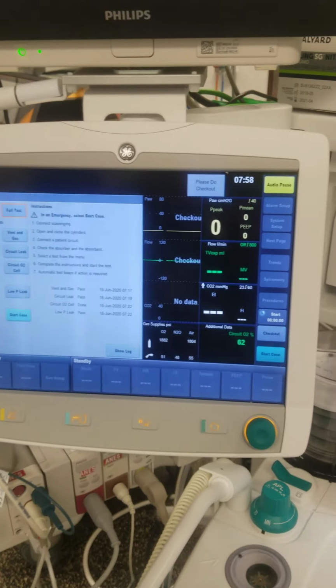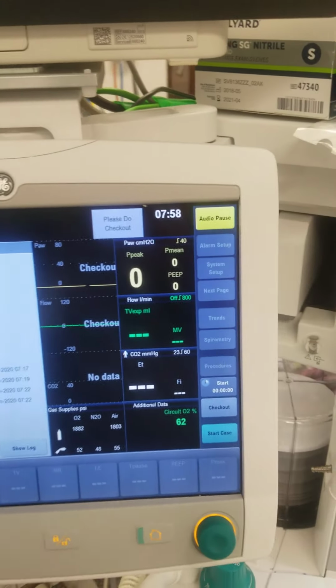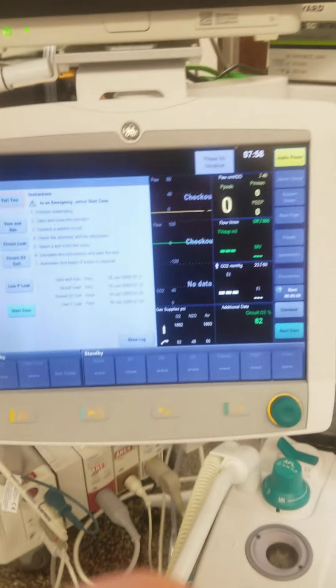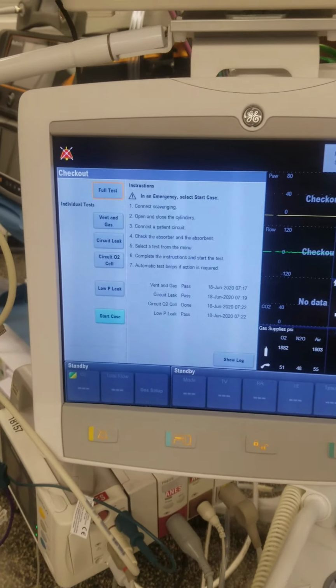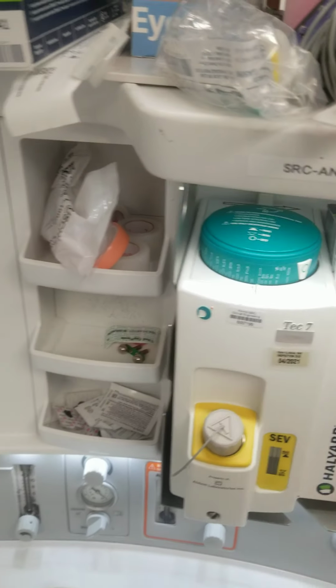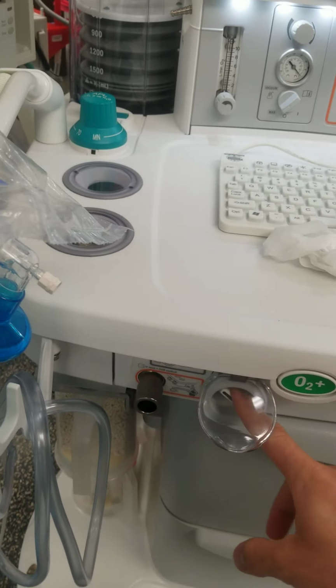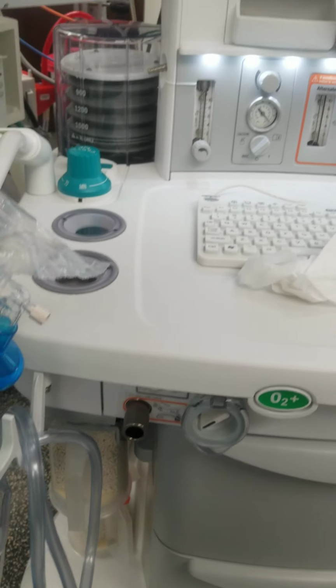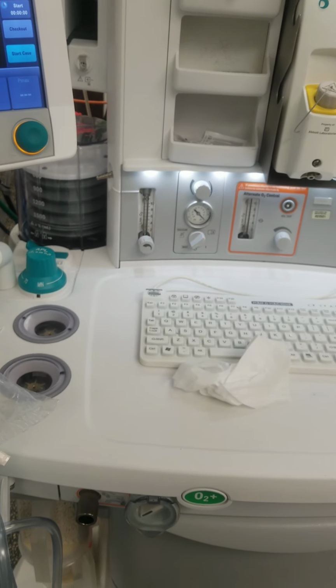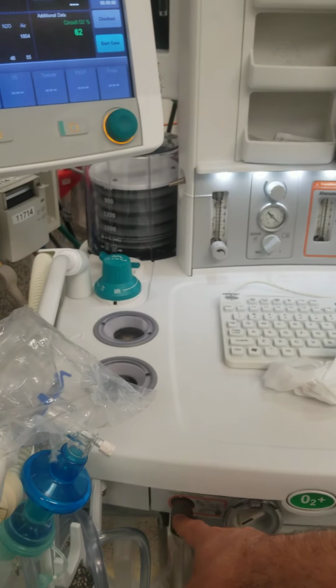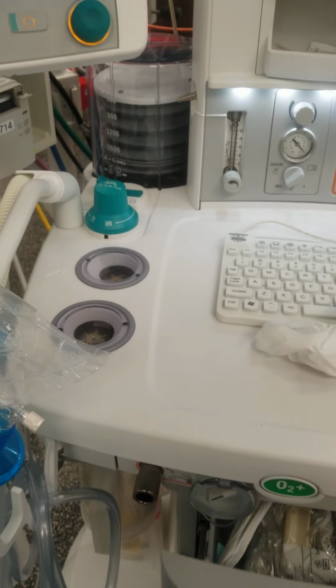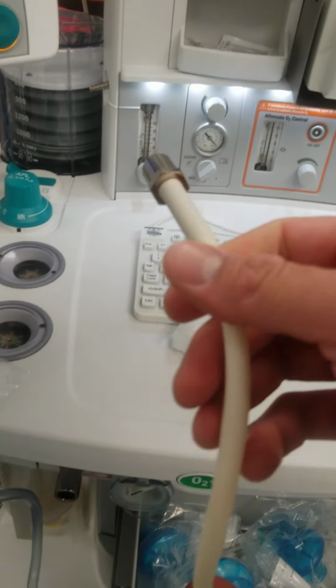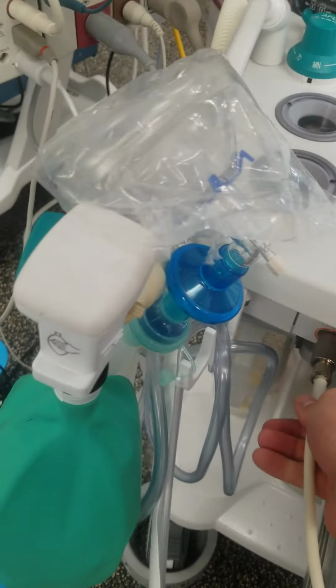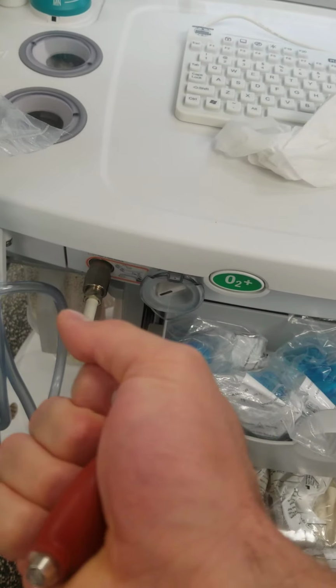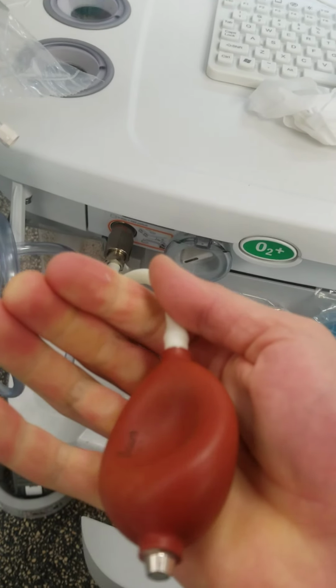All right, so my machine's on. It's telling me I have to do a checkout. So first thing I normally do is the low pressure leak test right here. So I'm going to turn my canister to 1%. I'm going to bypass my system to this little valve here, this common gas outlet. I'm going to grab my little bulb, and I'm going to squeeze this until all the air comes out, and it holds the suction.